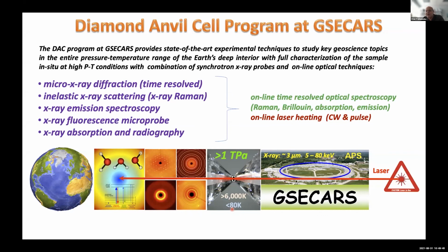And the toroid type, it's known for a long time that the toroid shape helps to reduce stress when we compress the sample. So basically it reduces the stress on the diamond and keeps it alive, not to break it. And then which one's the best out of those three? I was just curious. The best is the one that works for you. Okay, all right, thank you.